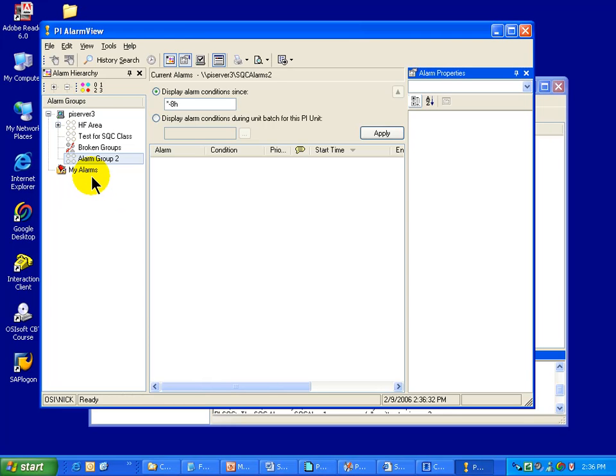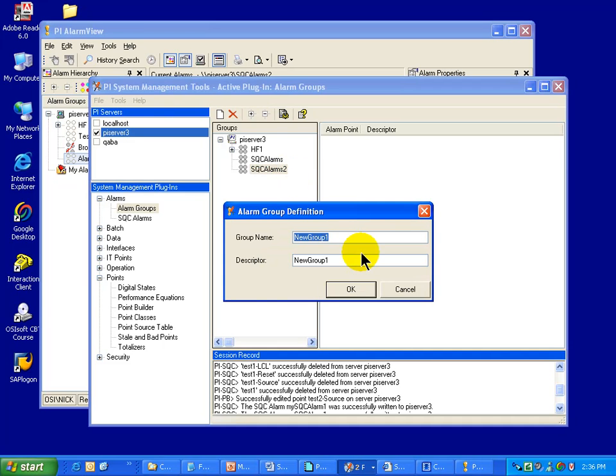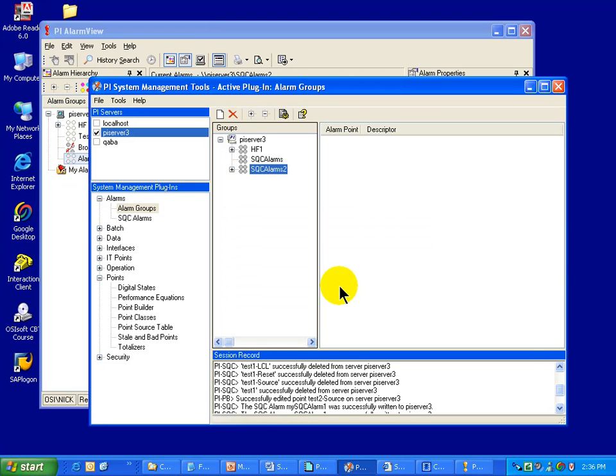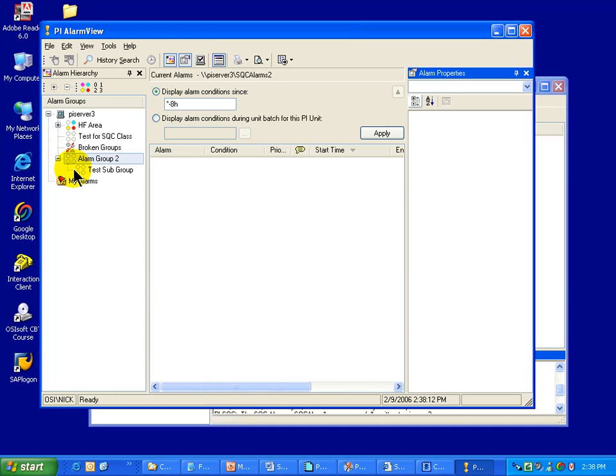That Alarm Group is now ready to make use of. I can go ahead and create Alarm Tags and then associate those with that Alarm Group. If I wanted to specify a subgroup within here, I just simply select the group that will be the parent and add a subgroup — I'll call this Subgroup 1. You'll notice it is the descriptors that show up in the Alarm Viewer. Now I've unpaused, and as you can see, I now have this subgroup and we're looking at the descriptors for each.